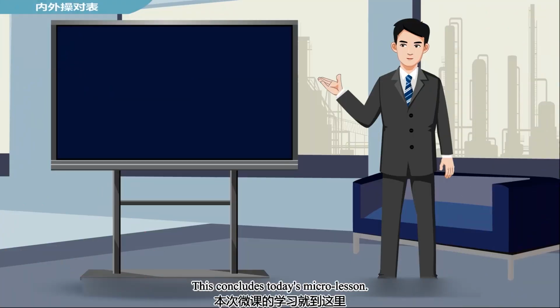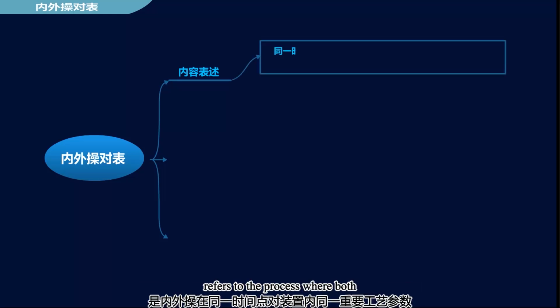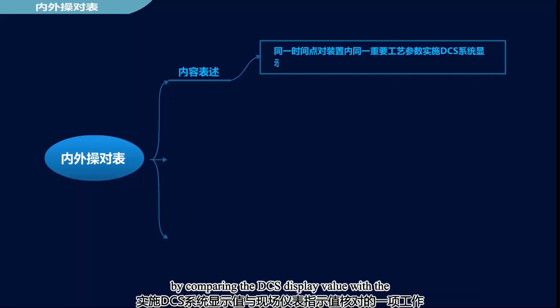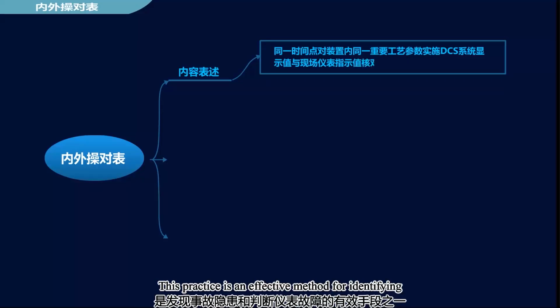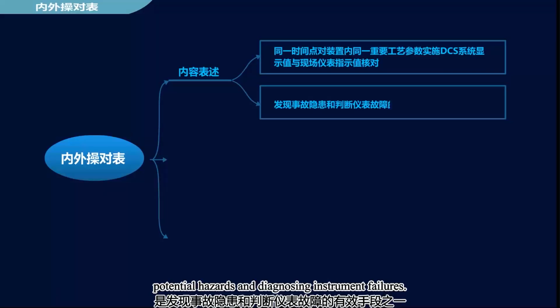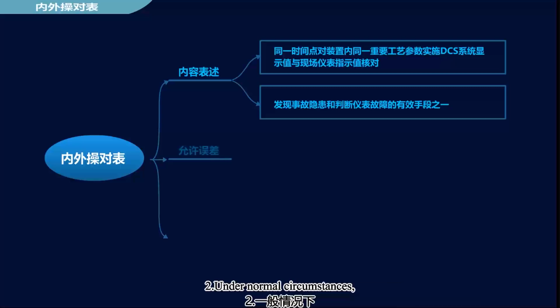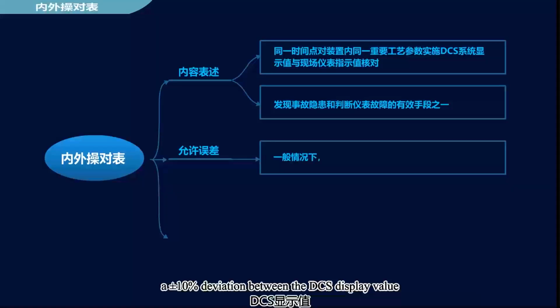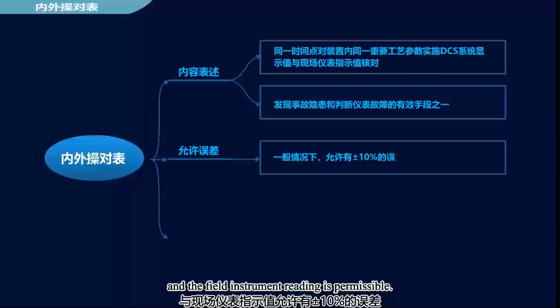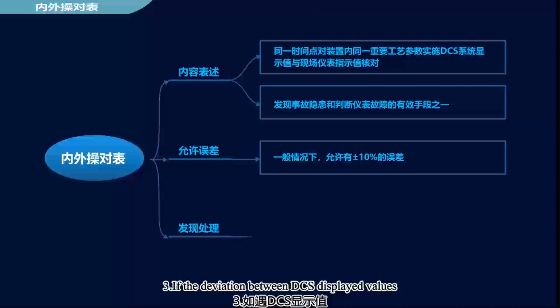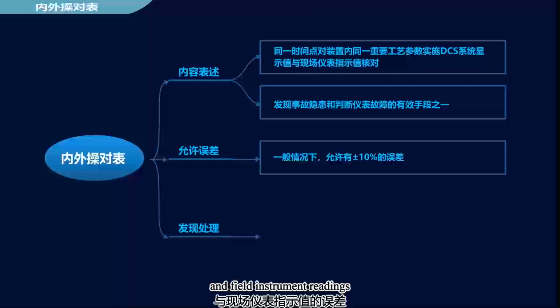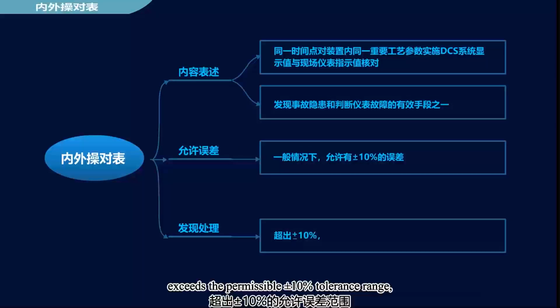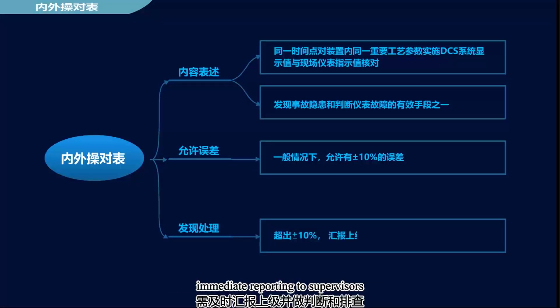This concludes today's micro lesson. Let's summarize the key points. First, cross-checking between control room and field operator refers to the process where both parties verify the same critical process parameter by comparing the DCS display value with the field instrument reading at the same time. This practice is an effective method for identifying potential hazards and diagnosing instrument failures. Second, under normal circumstances, a plus or minus 10% deviation between the DCS display value and the field instrument reading is permissible. Third, if the deviation between DCS displayed values and field instrument readings exceeds the permissible plus or minus 10% tolerance range, immediate reporting to supervisors is required for fault diagnosis and corrective actions.